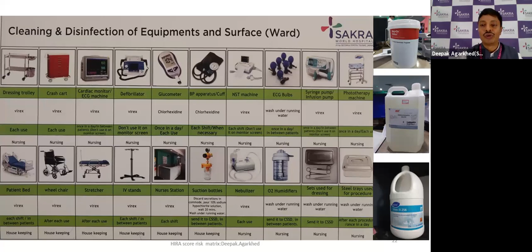A very, very important thing which needs to be looked into is traceability. When we do an audit, we often find that people may not be following the process of cleaning and disinfection based on the frequency. Now within COVID time, as you know, it's contact based and droplet. So it's necessary that we sensitize the team, nursing staff or paramedical staff, to do it exactly as per the protocols given by the manufacturers, and the infection control team and quality department can regularly audit so that the process of cleaning and disinfection for the medical equipment is being maintained.